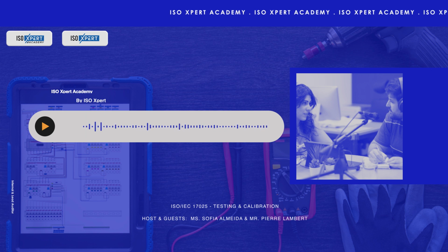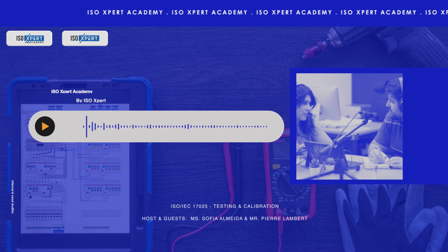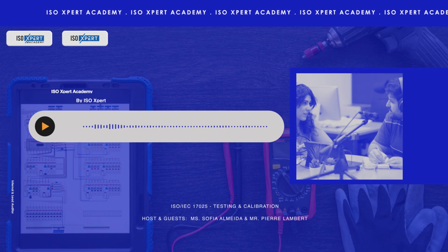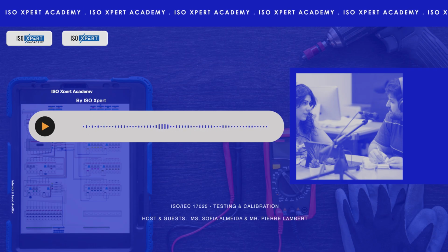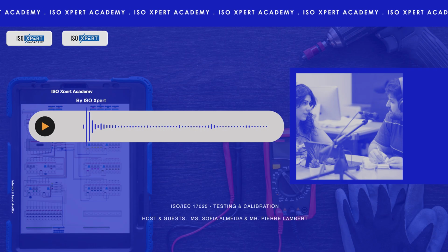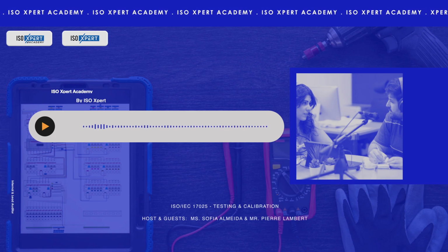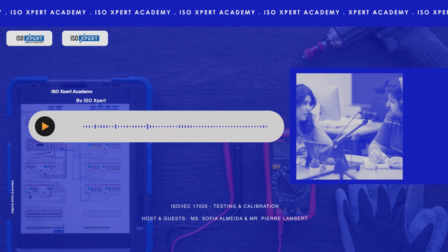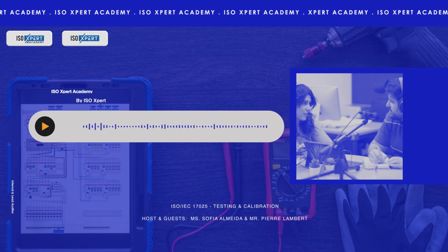Right, so break it down for us. What's first? First is 7.1, review of requests, tenders, and contracts. The lab has to be absolutely clear on what the customer needs before they start. Auditors check the contract review process forms, records, making sure the scope, the methods to be used, the requirements, it's all understood and agreed upon. No guesswork.